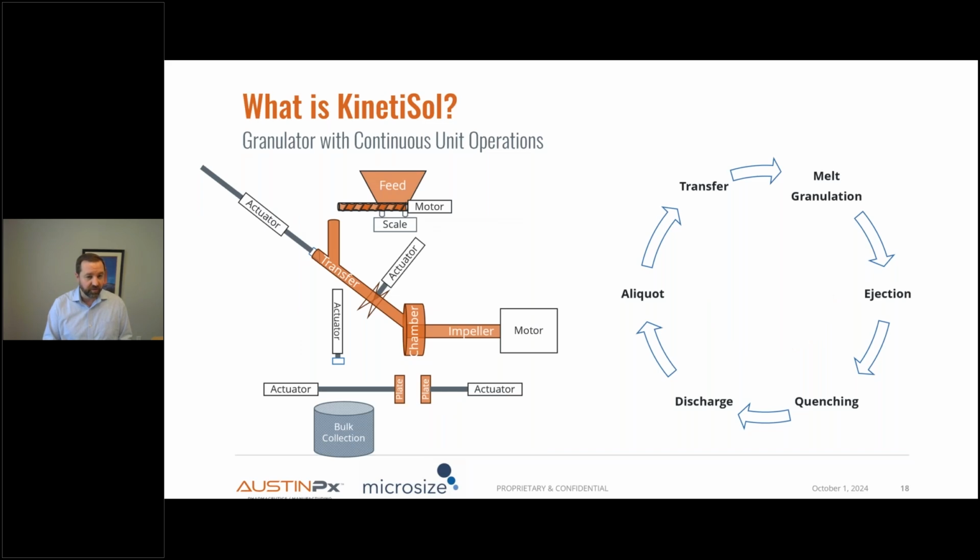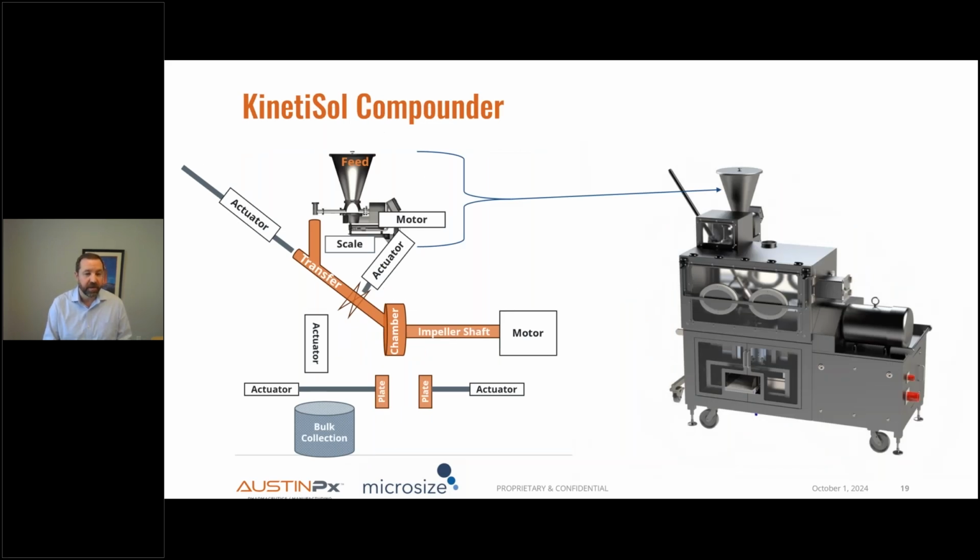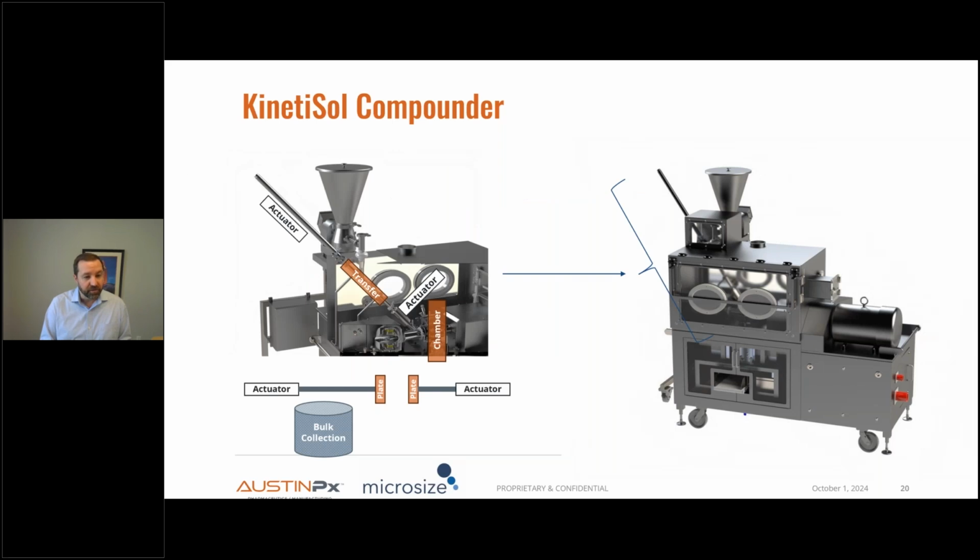Just to step into that a little bit more, the orange parts of this image on the left are the product contact pieces of a compounder, and I'm just going to step through how this aliquoting to discharging operation works for the audience. So the first thing that occurs is an aliquot is weighed out using a gravimetric feeder. This feeder is on a scale, so we can set the exact weight that we need for a given shot, and that material is put into what we call a transfer tube. When the machine is ready to process this shot in the compounding chamber and make it amorphous, this actuator opens, and another actuator transfers the material into the chamber. This is the transfer tube. And then once in the chamber, the process that I described earlier happens.